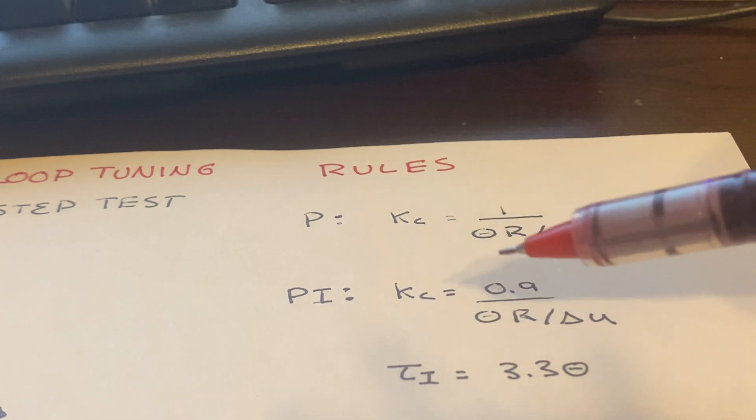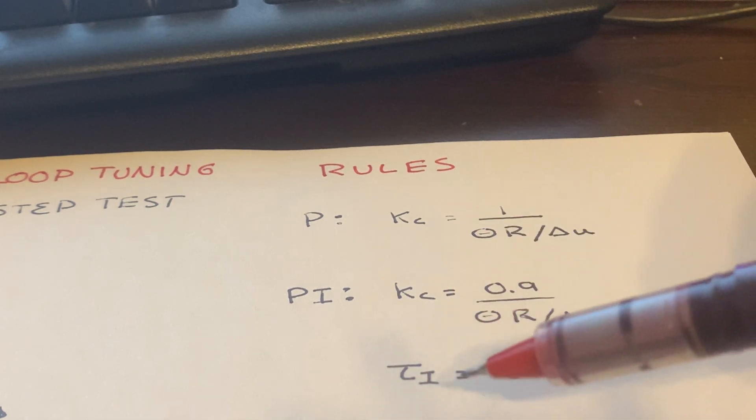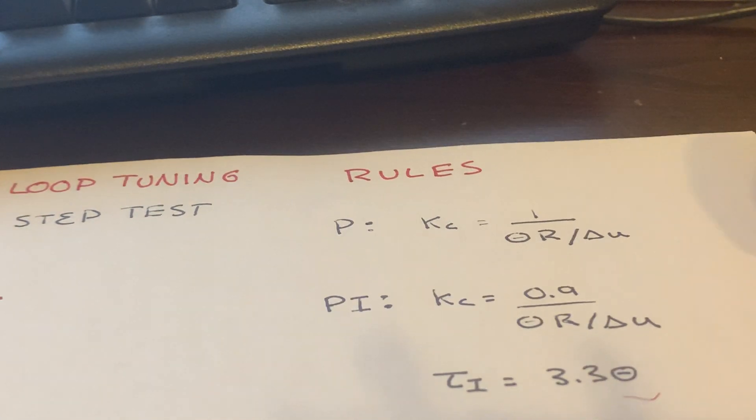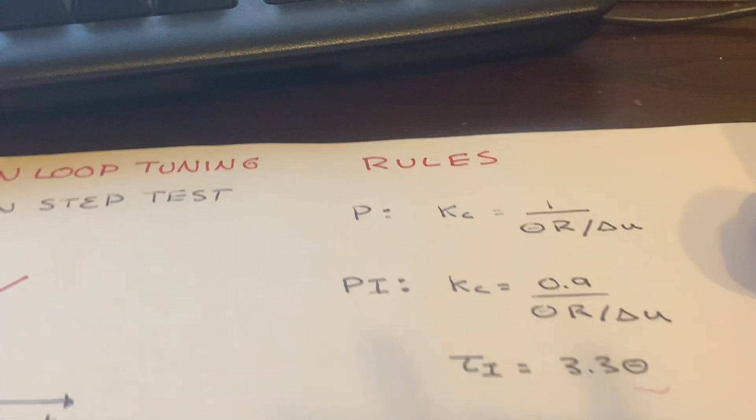For PI, it's Kc, which is the same rule for the proportional gain, except we're just tuning it down a little bit. So rather than 1, we're going to put 0.9. And then our integral time is just going to be equal to 3.3 times our estimate of our time delay. That's basically the tuning rule.